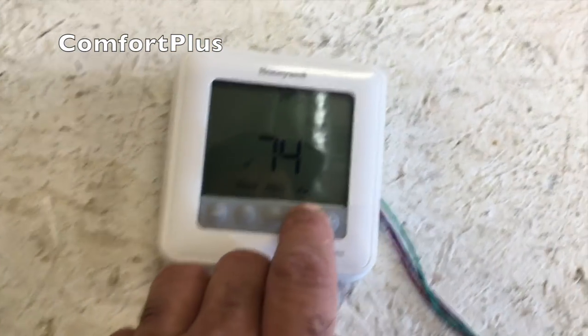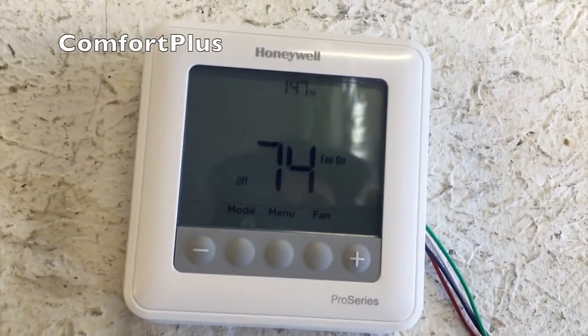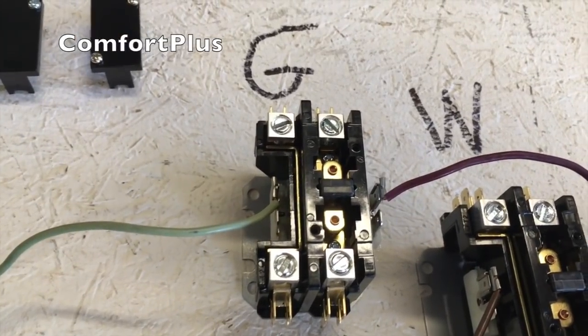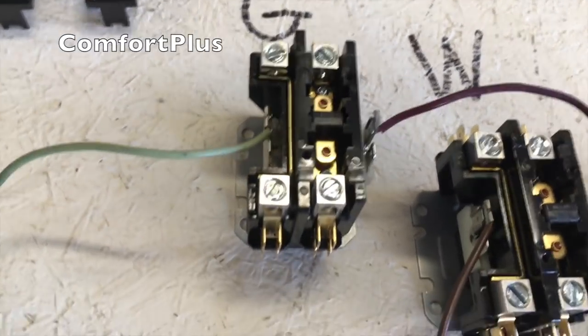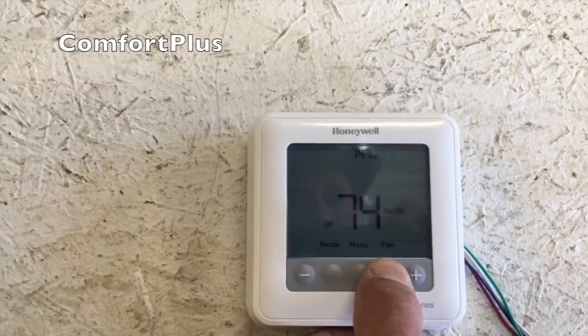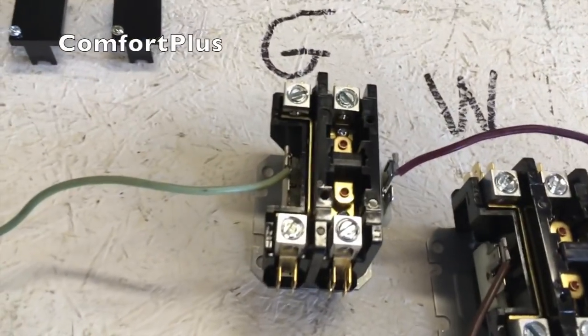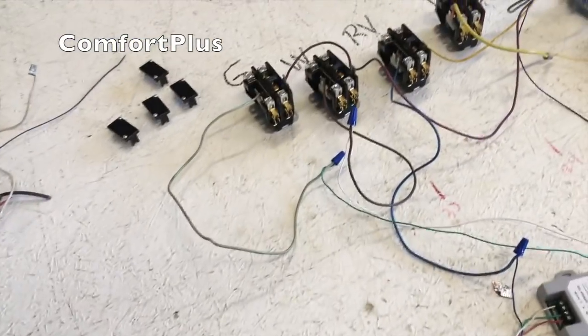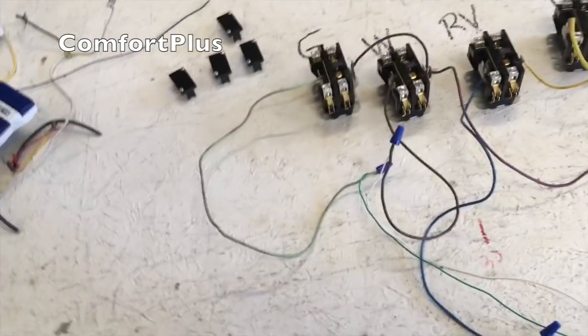So right now we're not pulling any amps on the red wire. Let's just try the fan first — fan to the on position. You can see the fan pulled in; the others are not pulled in right now. So right now we just have the fan. Turn the fan off, go back to auto. So after the delay it should drop the fan contactor back out — there we go. We know the fan works this way, which is promising because the fan is being run by that G terminal.